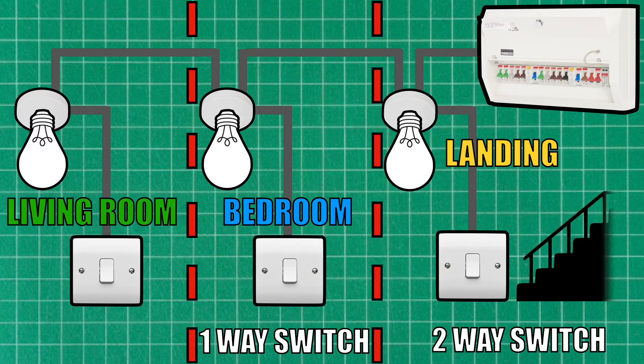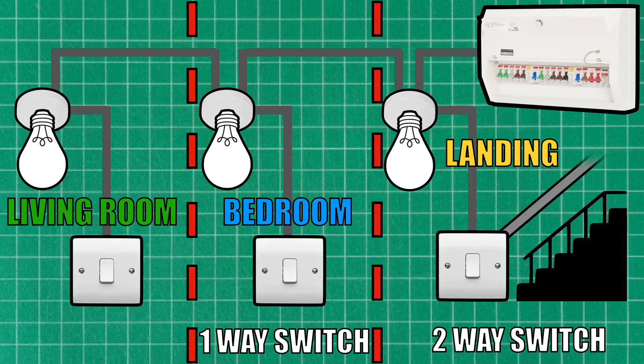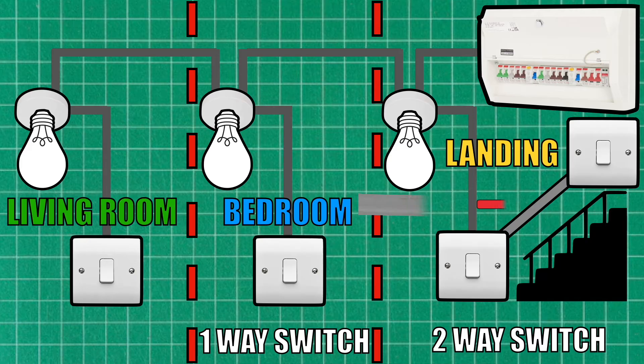So all we do is place one two-way switch at the bottom of the landing and then another two-way switch at the top of the landing. And we link the two switches together using something called three core and earth, and this just has an additional conductor compared to the normal twin and earth cable. So now we're able to operate our landing light from the top of the landing as well as the bottom.